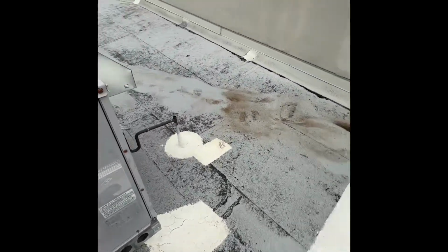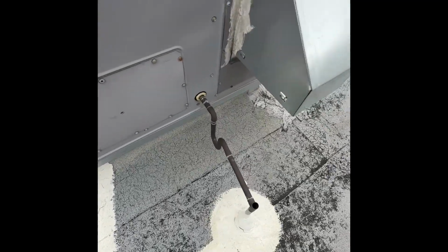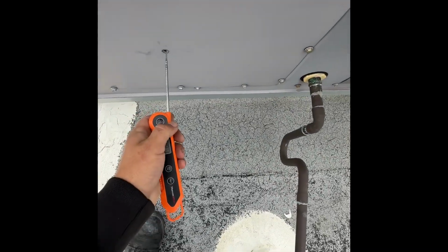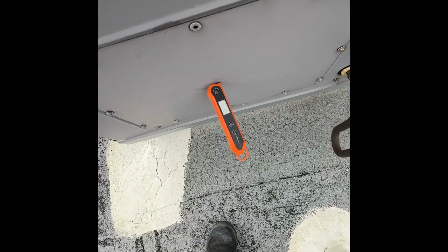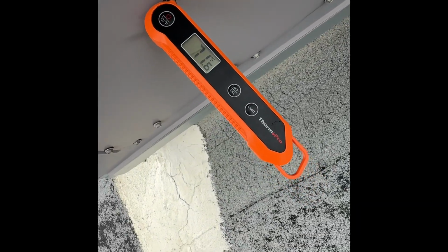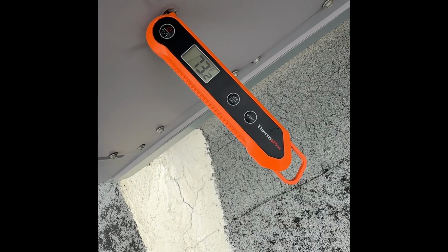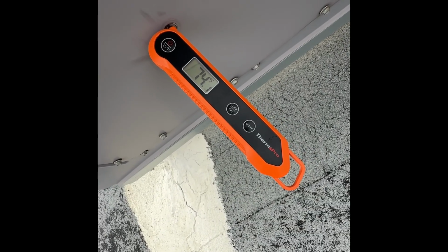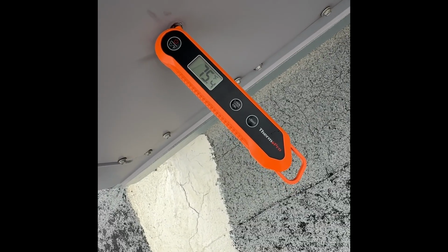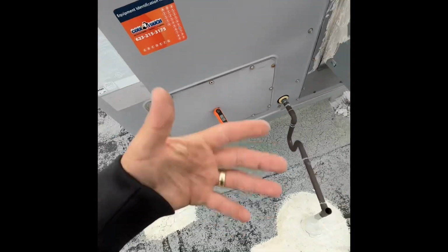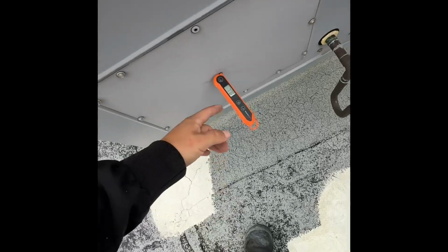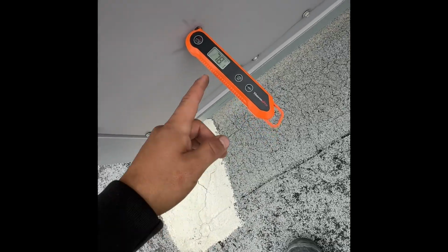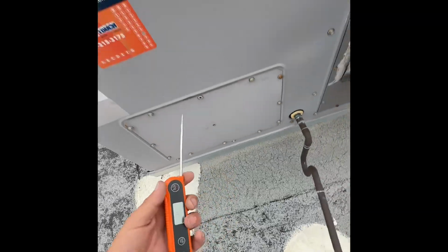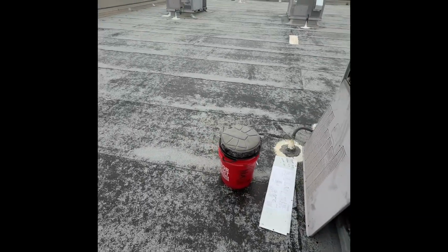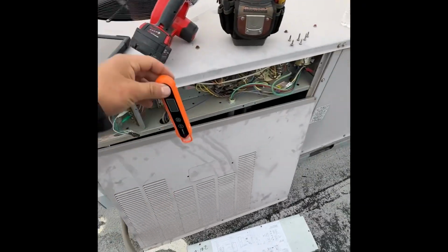Then we go back and we check just our supply, because we generally know our return air temperature is already 74 degrees, right? Double check our supply to make sure we're heating good. And as you can see, that's a lot different than 54 degrees like we had earlier. So we know this heat pump is running and heating. And it's gonna take a while to climb up in temp because the coil's still heating up from the cold freon that was running through it. So it's gonna take a while to climb, but this should be about 90 degrees once it's at full chat, running on all 10s. So yeah, that's pretty much it.